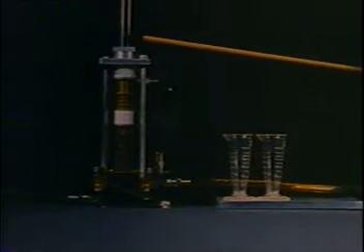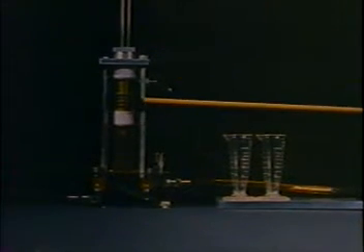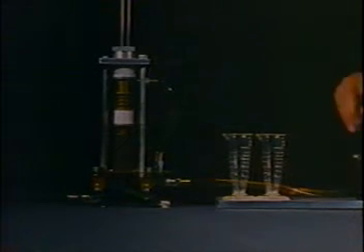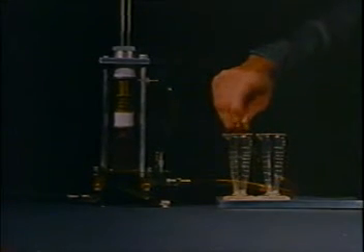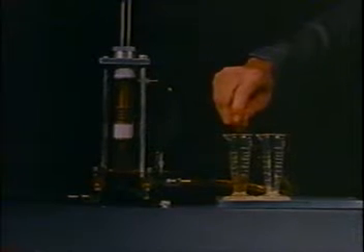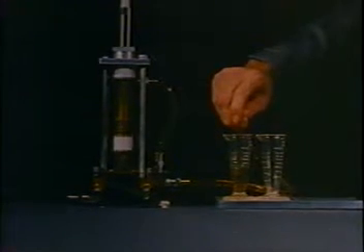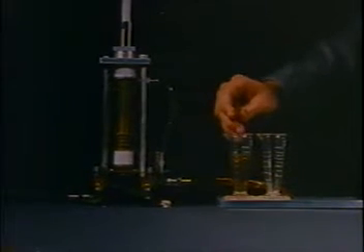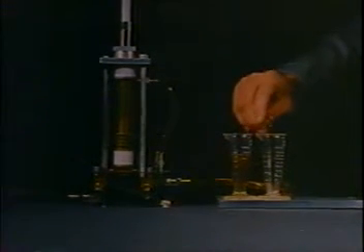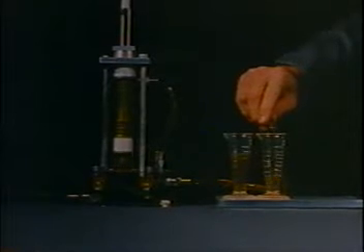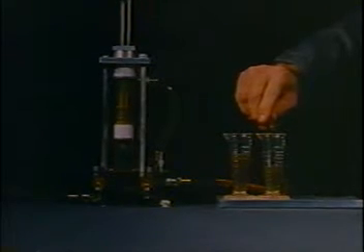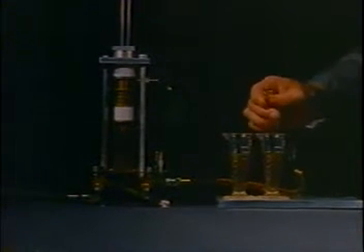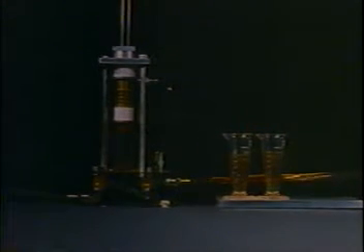By making the cross-sectional area of the piston rod 1/2 that of the cylinder, as the piston is pushed downward, the upper chamber increases in volume at 1/2 the rate that the lower chamber decreases. Therefore, on the downstroke, exactly 1/2 of the output from the lower chamber flows to the upper chamber, and exactly half flows out through the outlet. On the upstroke, the half which filled the upper chamber flows outward as the lower chamber refills.